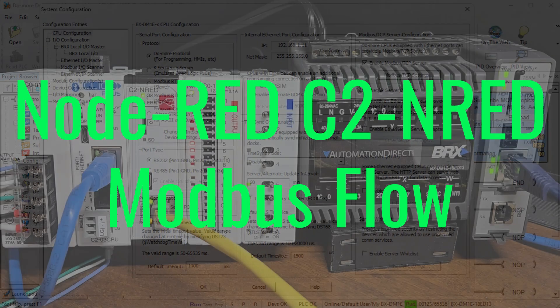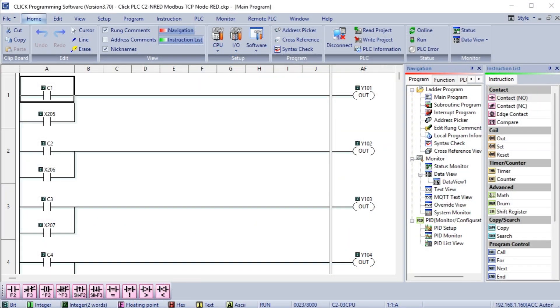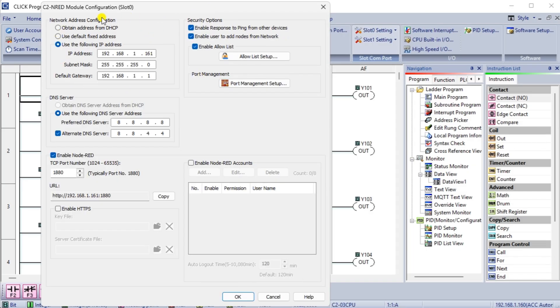We will now set up our Node-RED C2-NRED module for Modbus TCP communication. Using the Click Programming Software, we have connected to our Qlik Plus PLC and are viewing our previous Ladder Logic program where we installed the Modbus nodes. Call the C2-NRED module configuration window by selecting C2-NRED under the main menu Setup, Slot 0 setting. You will see the static IP address for the Node-RED module and the setup parameters we have discussed previously.